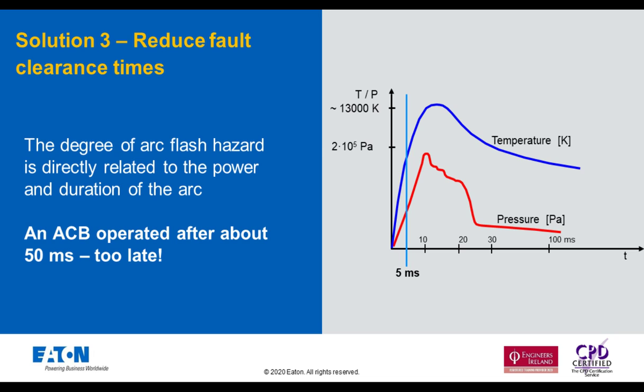The arc produces a mixture of toxic combustible waste and molten particles, generally liberated as copper, steel and plastic components, which get vaporized if the arc is left to burn. This type of environment is extremely dangerous to personnel in the vicinity, because the protective devices cannot operate fast enough to clear the fault before the build-up of temperature occurs when you're just relying on the ACB to operate.